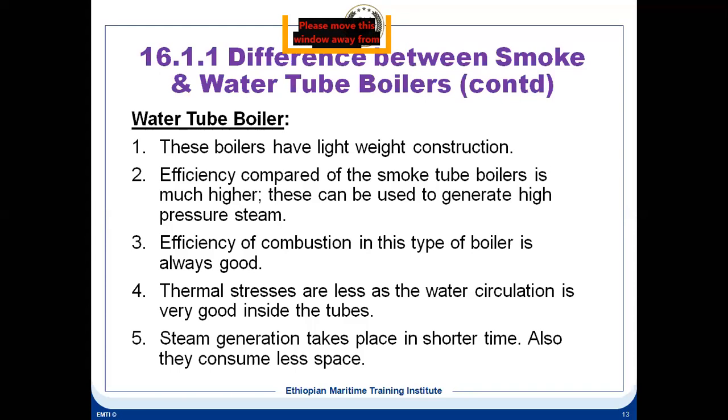And a small water tube boiler will consume less space. So from a ship owner's point of view, water tube boiler makes much more sense. Firstly, it has a lightweight construction, so it does not require that much under deck strengthening. And since the weight of your equipment is less, the weight of the cargo which you can carry obviously will be more, and you can earn much more freight.